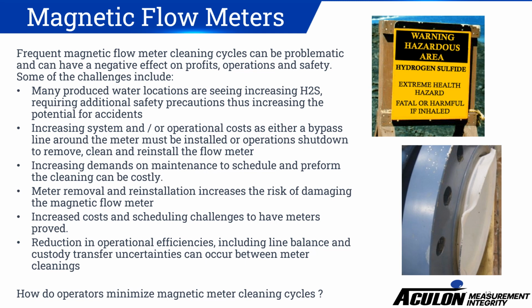Increasing demands on maintenance to schedule and perform the cleaning can be costly, especially as the cleaning frequency and the number of meters increase. Then there's the cost of the meter's removal and reinstallation. Each time this is done, the risk of damaging the magnetic flow meter increases. There are costs and scheduling challenges to have meters proved, and then depending on the actual cleaning cycle, a reduction in operational efficiencies, including line balance and custody transfer uncertainties, can occur between meter cleanings. So how do operators optimize magnetic flow meter cleaning cycles?